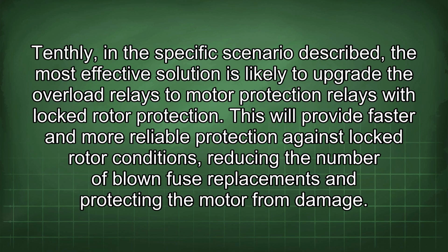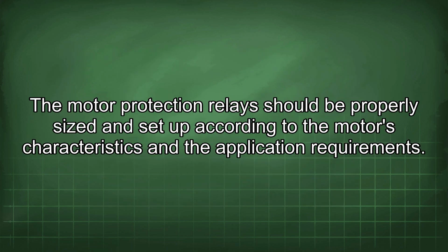Tenthly, in the specific scenario described, the most effective solution is likely to upgrade the overload relays to motor protection relays with locked rotor protection. This will provide faster and more reliable protection against locked rotor conditions, reducing the number of blown fuse replacements and protecting the motor from damage. The motor protection relay should be properly sized and set up according to the motor's characteristics and the application requirements.